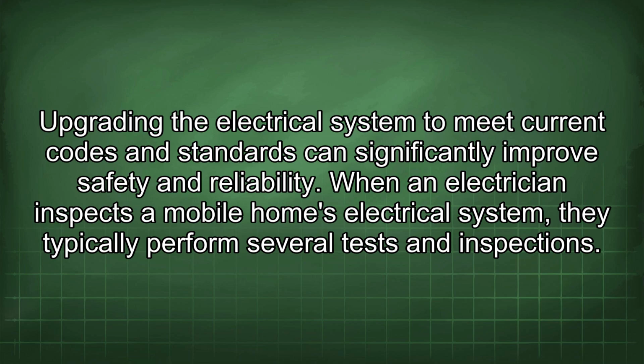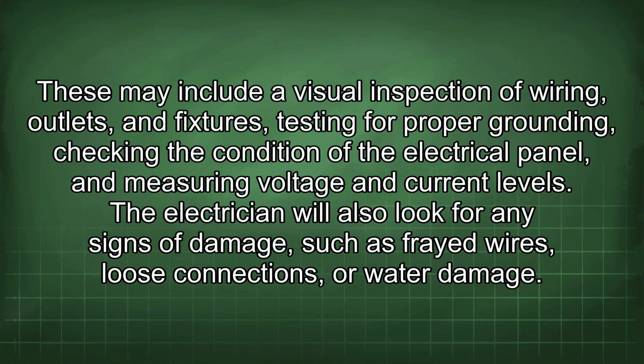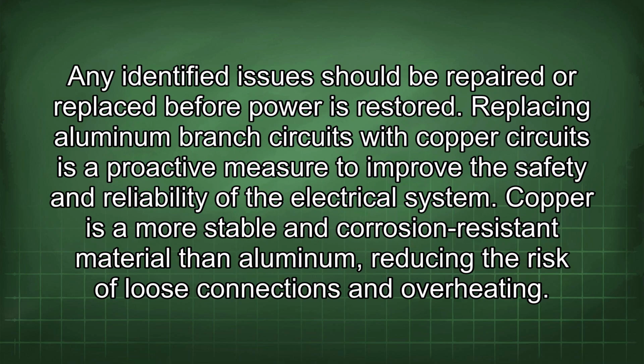When an electrician inspects a mobile home's electrical system, they typically perform several tests and inspections. These may include a visual inspection of wiring, outlets, and fixtures, testing for proper grounding, checking the condition of the electrical panel, and measuring voltage and current levels. The electrician will also look for any signs of damage, such as frayed wires, loose connections, or water damage. Any identified issues should be repaired or replaced before power is restored.